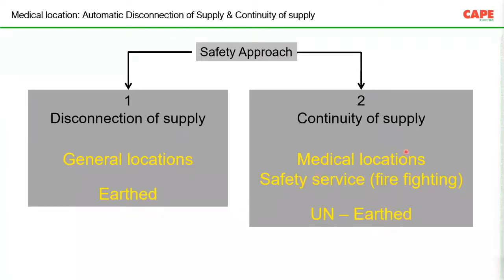Also, for fire services, for firefighting systems, you can use a technique for continuity of supply, which is called an unearthed system. So basically, electrical systems are classified into earthed and unearthed systems. Earthed system means your MCB should trip immediately. Unearthed system means your MCB need not trip during the first fault.